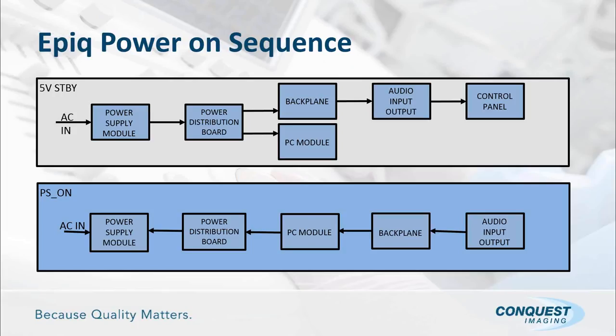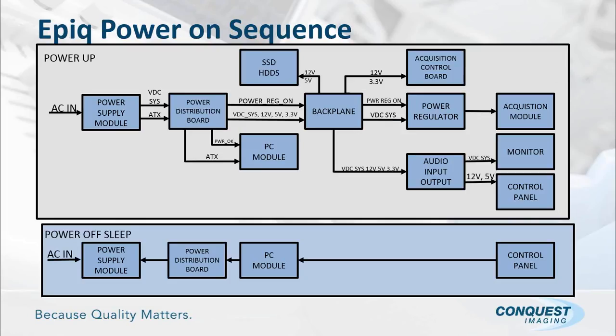At that point, moving on to the next box, power supply on, you still have your AC input in there, and what happens is the operator presses the power button, and that signal then goes back through the audio input output module, through the backplane, through your PC module, through the power distribution board, and back into your platform power supply module, and that now gets the power supply on signal and basically engages itself. So now we have the system getting the command to power on.